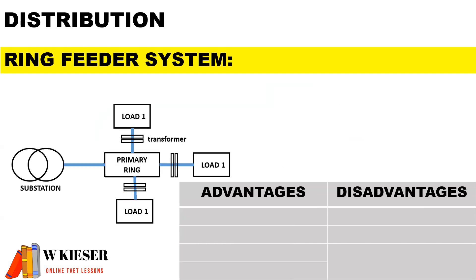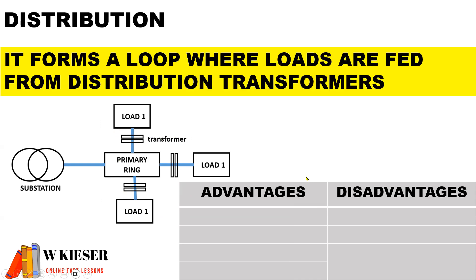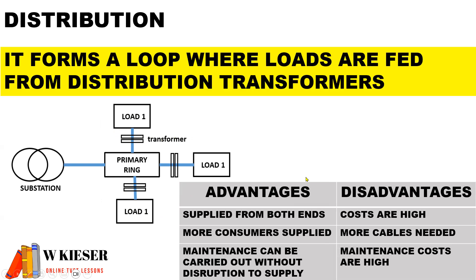For the ring feeder system, you'll notice that we have a type of loop that is being supplied, so you can supply your load from different sides and not just one side. In terms of the advantages, it is supplied from both ends, more consumers are supplied, and maintenance can be carried out without disruption to the supply. However, for the disadvantages, the costs are higher, more cables are needed and the maintenance costs start to increase.